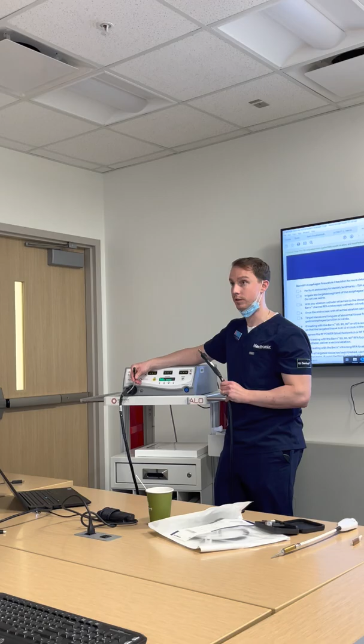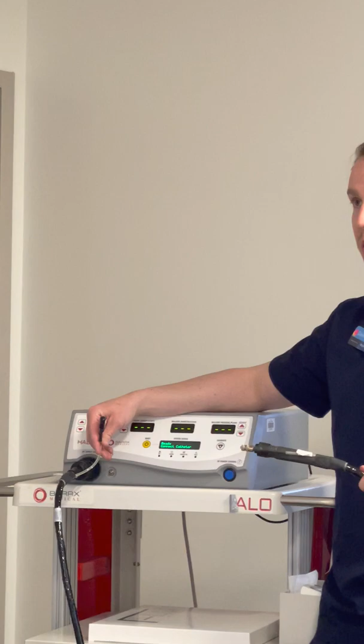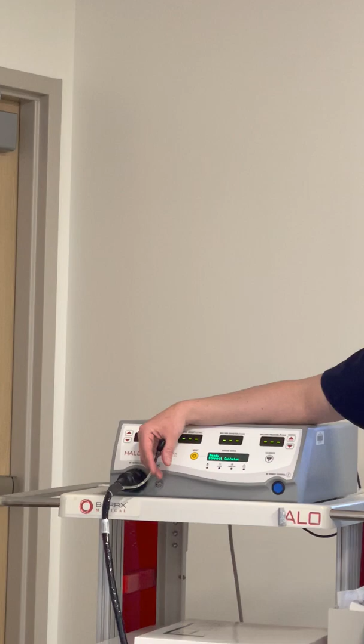The other piece that we typically forget is we need to connect this cord. This is super important for the 360 Express. Let's just get in the habit of plugging in every single time. It doesn't matter if we're using the focal or not. If this thing is not plugged in and we go to use the 360 Express, well, if this isn't plugged in, it won't inflate. And then we'll get an error on the system and it will cause some headaches and we'll start to go through our troubleshooting. But if we just get in the habit for every single case, please plug this in and it just clicks on. What you can do is just lightly pull back on it just to make sure that it's secure on there.